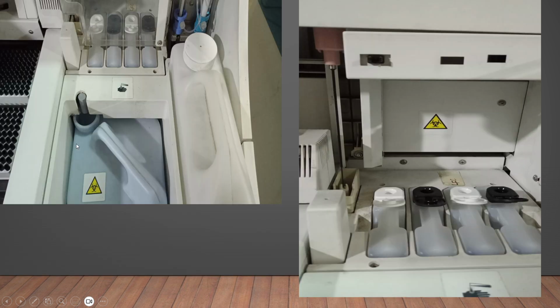So then this is the liquid waste. Now the liquid waste has got a sensor, so without it, when you start, it will give a big alarm. Okay, so you have to ensure that when you are switching on the instrument, these are in position, right? So next one is the procell clean cell. Procell clean cell is under a cover. There is a door which prevents access, so that nobody touches it and all.